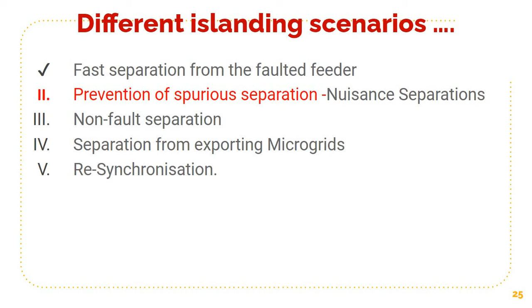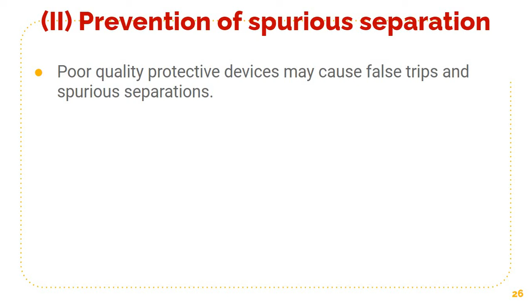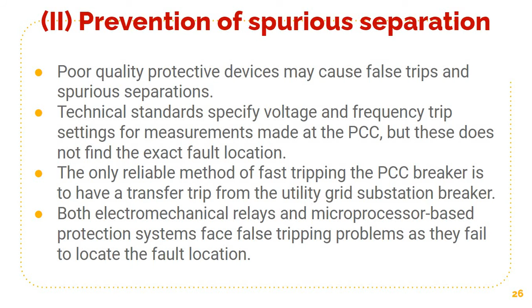So now we come to the prevention of spurious separation, or what we also call nuisance separations. The main reason for spurious separation is the poor quality of protective devices. The technical standards specify voltage and frequency settings for measurements made at the PCC, but this does not find the exact fault location. So the only reliable method of fast tripping the PCC breaker is to have a transfer trip from the utility grid substation breaker. Even if you go for microprocessor based protection systems, they also face false tripping problems because they fail to locate the fault location.